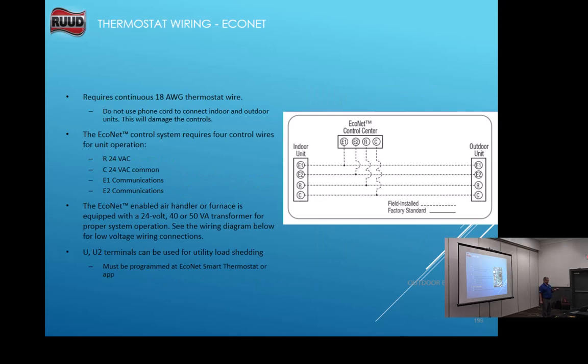If you have an EcoNet thermostat, all you need are 4 wires anywhere, from the thermostat to the air handler or furnace, and from the furnace or air handler to the outdoor unit. All you need is 4 wires, no matter whether it's straight cool, 2-stage, or heat pump. That's all you need with the EcoNet thermostat. Okay?